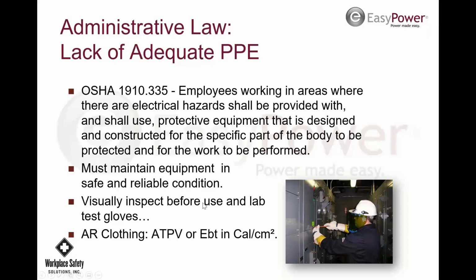One thing I learned, I was doing an arc flash analysis. I was doing some data collection, and I put a hood on to go into a 208 transfer switch, a hood with my coveralls and so forth. And I put the hood on, and a bug goes across the screen, and I go to brush it off, and it was actually on the inside. So I closed the door to the transfer switch, threw off my hard hat, and I didn't know if it was a brown recluse spider or what it was. But anyways, I learned from that event that I need to inspect my hood every time before I use it, because I may not use it for a year or two, and who knows what can crawl into this thing in that amount of time. So that's another thing to do, is visually inspect it.